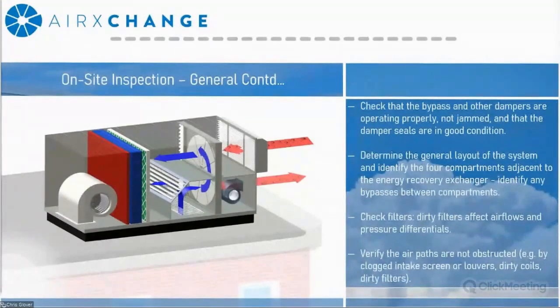Continuing on, you're going to want to check that the bypass or any other damper in the system is operating properly, that they're not jammed, and the damper seals are in good condition. You're going to want to identify the general layout of the system. Look for areas where there can be potential bypass around components. Once again, this could be from missing fasteners or panels.